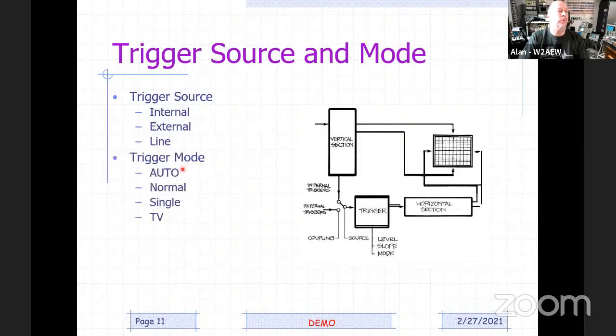The trigger mode, we'll talk about auto here in a moment, but there's auto trigger mode, and there's normal trigger mode, which basically says, I'm going to get a sweep when I get a trigger. That's what you're using most of the time. You might actually use auto most of the time, but again, we'll talk about that in a minute. A single trigger would just give you a single trace in response to a trigger and stop. For an old analog scope, that's not terribly useful unless you've got a scope camera to capture that trace, but it's there. Also, a lot of the older scopes have a TV trigger mode that allows you to trigger on the NTSC composite video signal to look at either horizontal lines or vertical sync pulses and trigger on those.